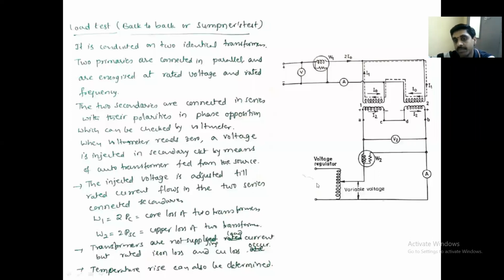After that, we will inject, that means we will supply voltage from this side so that the rated current flows in this. Then the wattmeter reading gives the copper loss, which is 2 times the copper loss of each transformer. That is the way we will conduct the test: first assuring 0 voltage, next applying rated voltage and noting the wattmeter and ammeter readings, and after that injecting current into these series connected transformers and noting the wattmeter and ammeter readings, which give the iron loss and the copper loss. So W1 is equal to 2 PC, and W2 is equal to 2 PSC, the iron loss and copper loss for two transformers.